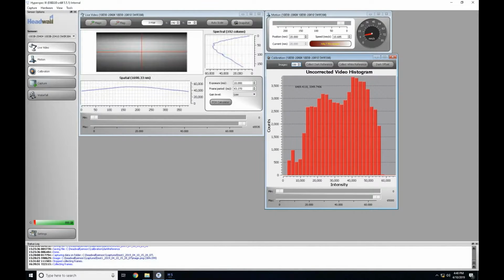And so that will be the relative amount of light that's reflected from your sample, and that is where all of the chemical information is contained. And so that's really what we want to get to. But we're always just measuring how much light is actually getting to the detector, which, as you can see, depends on your light source. It depends on the optical characteristics of your system.